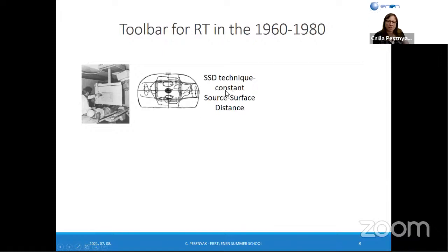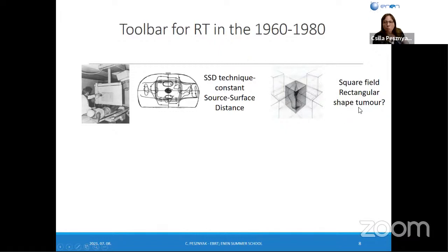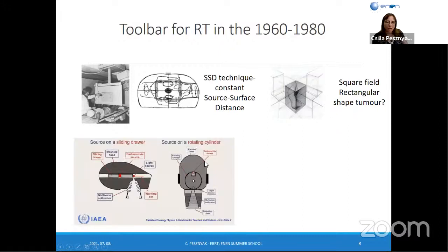That means that they use a constant source surface distance. For the linear accelerator, this source surface distance is 100 centimeters. For the cobalt unit it is 80 centimeters. And we can also irradiate only with a square or rectangular field, but we know that the tumor shape is not rectangular. It's changeable. You can see here also the construction of the cobalt unit. At that time mostly cobalt units were used, but for example, the Varian company had accelerators. It's named CLINAC, with 4 MV and 6 MV.